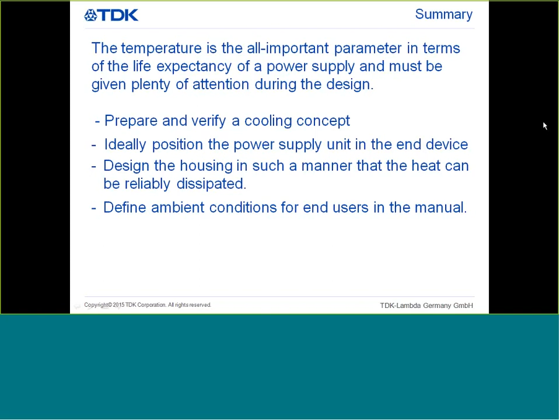The temperature is the all-important parameter in terms of the life expectancy of the power supply and must be given plenty of attention during the design. Prepare and verify a cooling concept, ideally position the power supply unit in the end device, design the housing in such a manner that the heat can be reliably dissipated, and define ambient conditions for the end user in the manual.